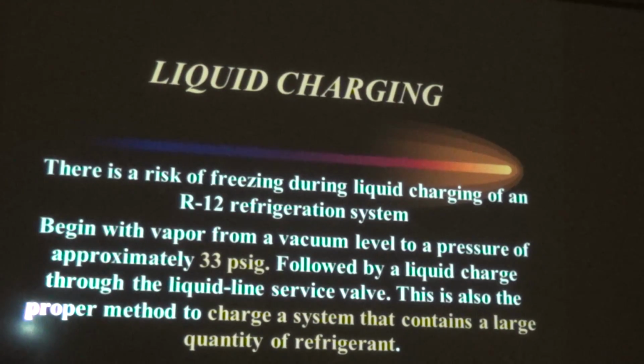Liquid charging. Liquid charging is common with large Type 2 equipment, and it tells us here there's a risk of freezing during liquid charging of a system that uses R12. Begin with vapor from a vacuum level to a pressure of approximately 33 pounds PSIG if you're using an R12 refrigerant. Then you can continue your charge as a liquid charge. The reason why we bring it up to 33 pounds is that's above freezing for systems that use R12.